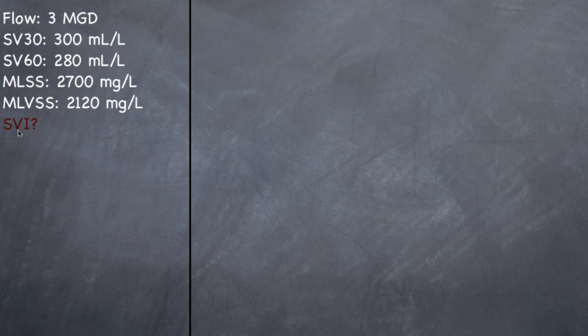All right, SVI. SVI stands for Sludge Volume Index, and it's a really easy problem. It's not that labor intensive. So we have a flow of 3 MGD, a settling volume SV at 30 minutes of 300 milliliters per liter, a settling volume at 60 minutes of 280 milliliters per liter, MLSS 2700, MLVSS 2120. Too many SSs. They want to know what the SVI is. SVI basically means how well the sludge is going to settle in your secondary clarifier, the tendency for it to settle.